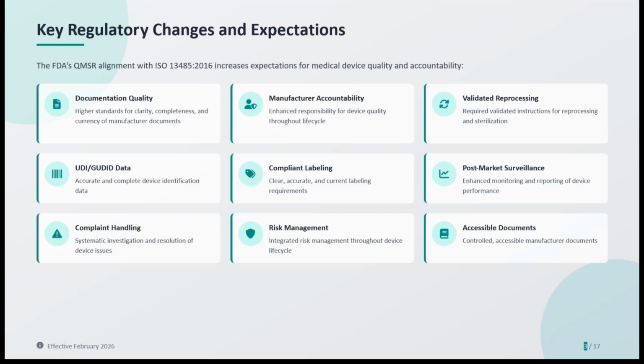Here we're outlining how QMSR aligned with ISO 13485 raises expectations across documentation quality and accessibility, UDI and GUDID data accuracy, labeling, again including those important reprocessing validations, post-market surveillance, and complaint handling. One very practical point is around post-market surveillance and complaints. In Xcelrate UDI's platform, our clients don't have to reinvent the wheel to report a device issue. They can select the device directly in our platform, apply the appropriate IMDRF term, and the documentation of the complaint or device failure or contamination is generated in seconds. That single action supports FDA expectations, manufacturer required processes, and the hospital's internal quality review. And it does so in a way that is structured, standardized, and traceable.